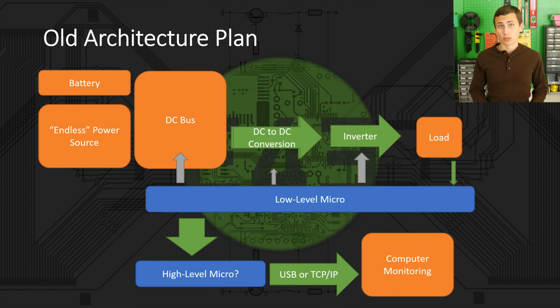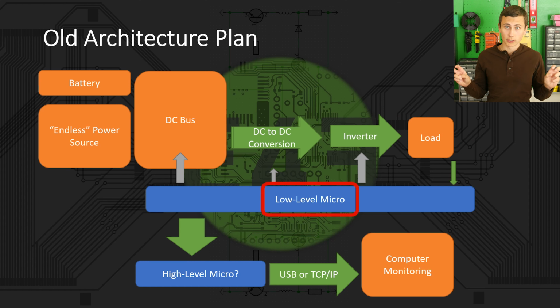The last major issue is surrounding the so-called low-level micro. This micro is controlling things on both sides of an isolation boundary with no provisions or plan to isolate the signals or high voltage from the user, batteries, etc. This is a huge fundamental flaw, and we need to change that.